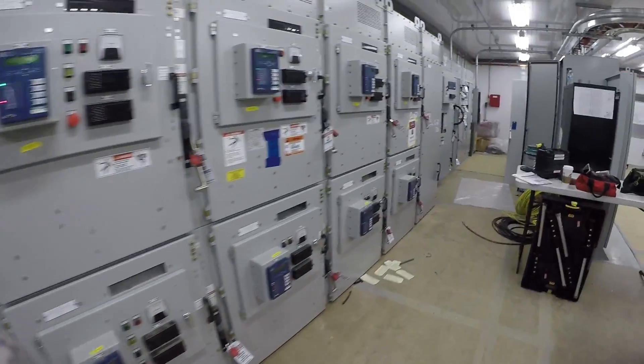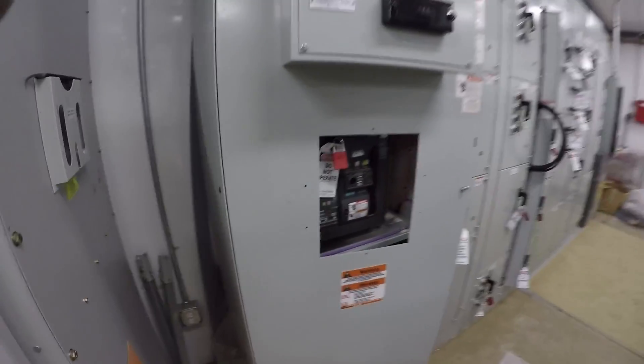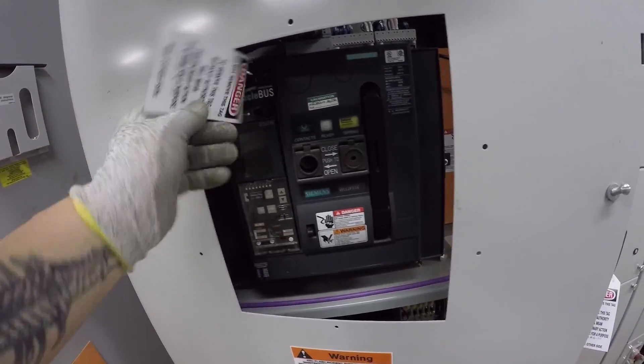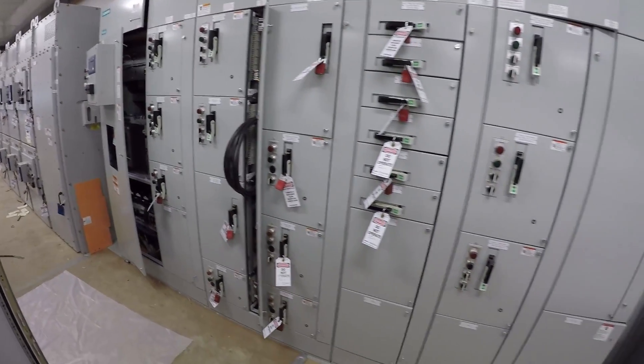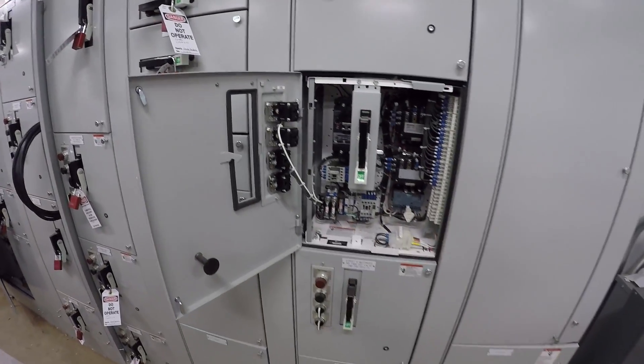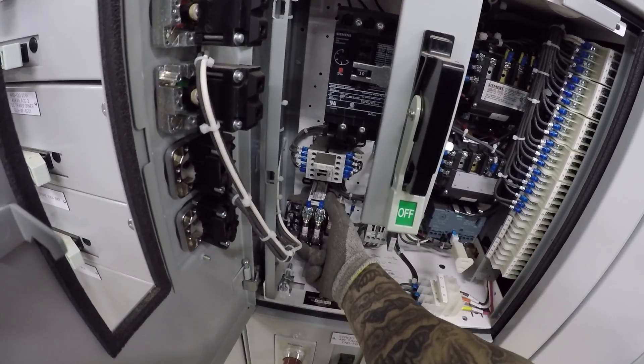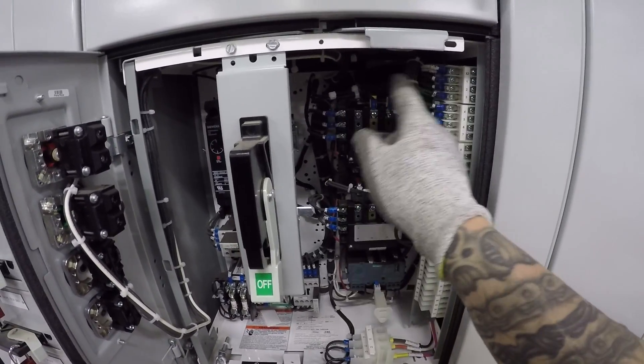I'm in the MCC house right now. There's my tools. Breaker is open, locked out. These are the buckets we're working on here — MCC buckets. Our task is to replace these control power transformers right here and do some rewiring with this circuit right here.